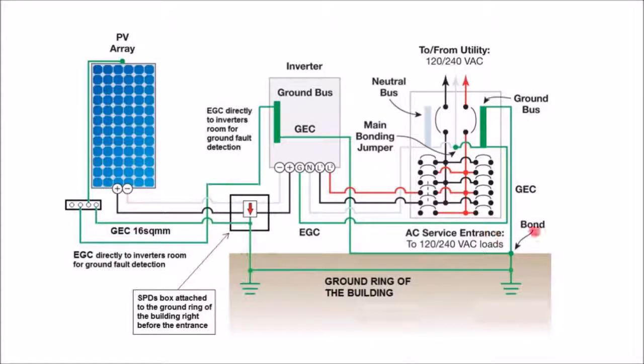interconnected grounding system, and there are special rules on what constitutes a grounded system. So often with solar arrays, you actually need two grounding electrodes rather than one grounding electrode, particularly when you're using ground rods. And so we see two grounding electrodes here. Actually, they're using it in the form of a ground ring. We're going to talk about that in a minute. And then we see there's no neutral wire in the solar array. It's a DC system with a positive and a negative. But in that combiner box, nowadays, it's not uncommon to run a neutral wire up to the rooftop anyway.